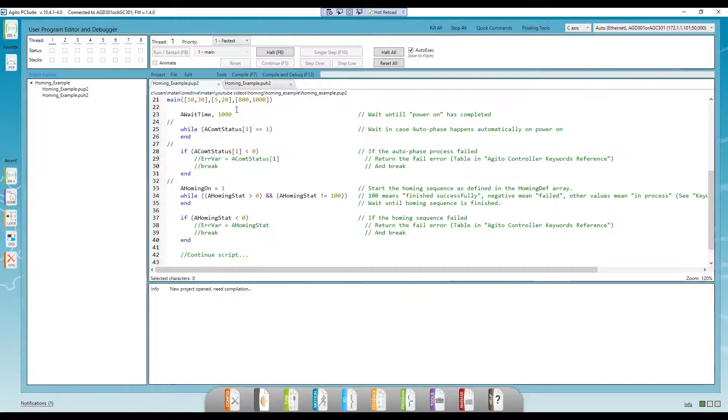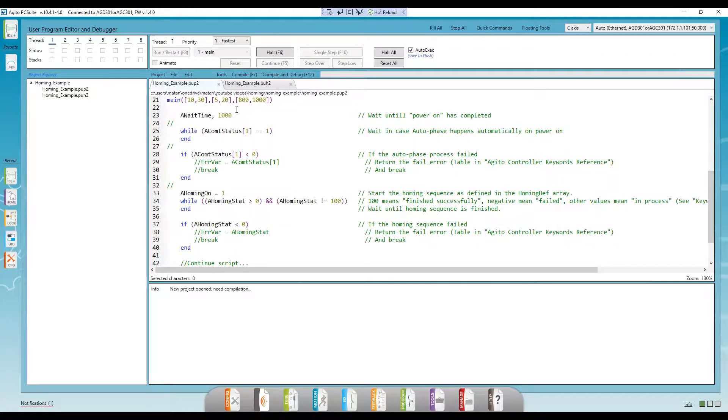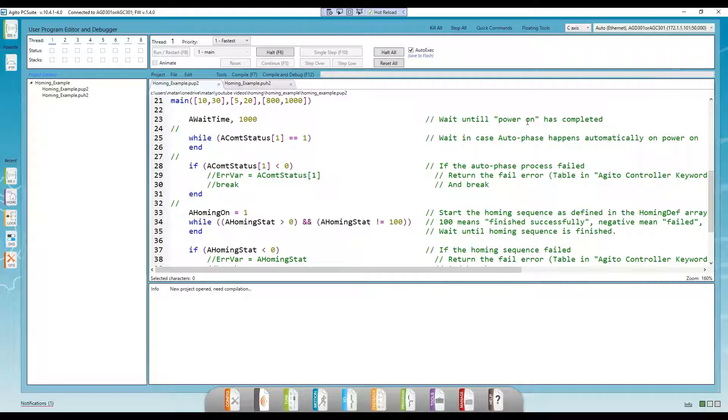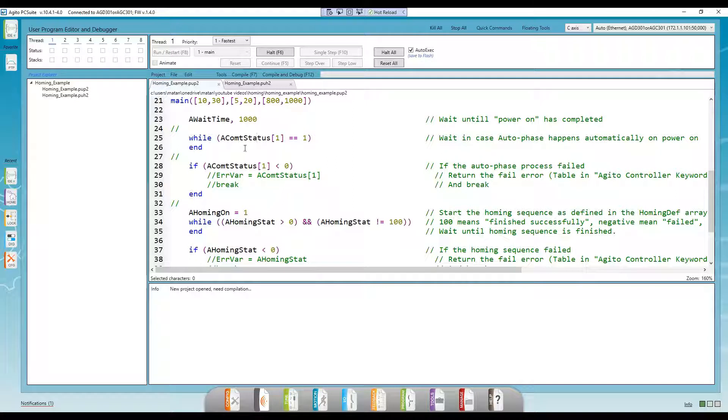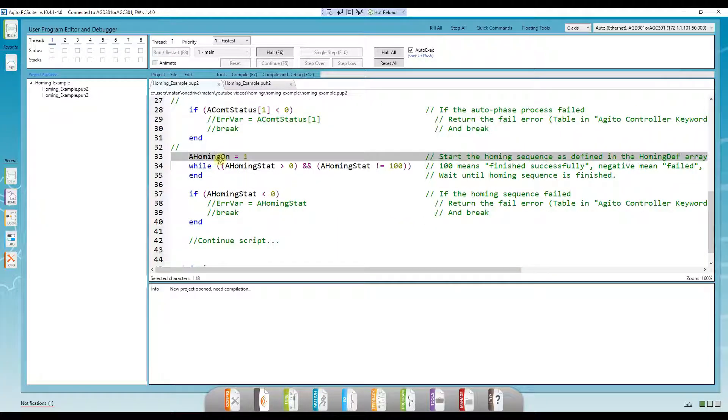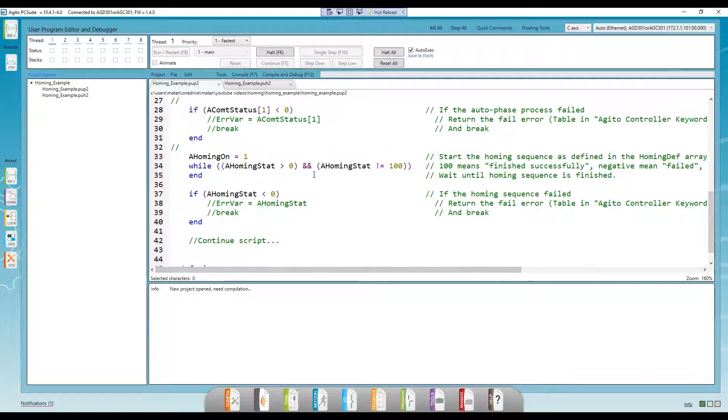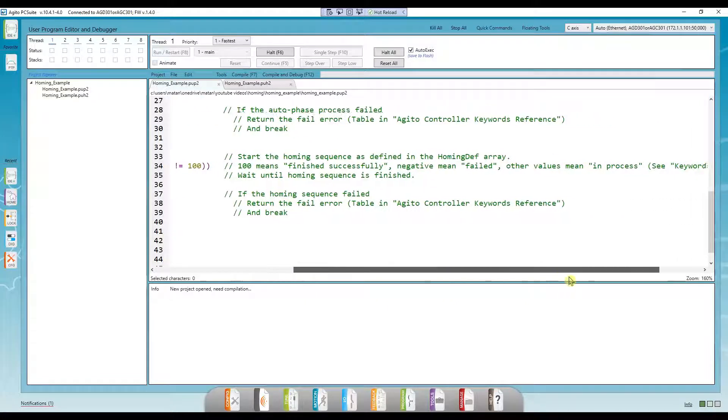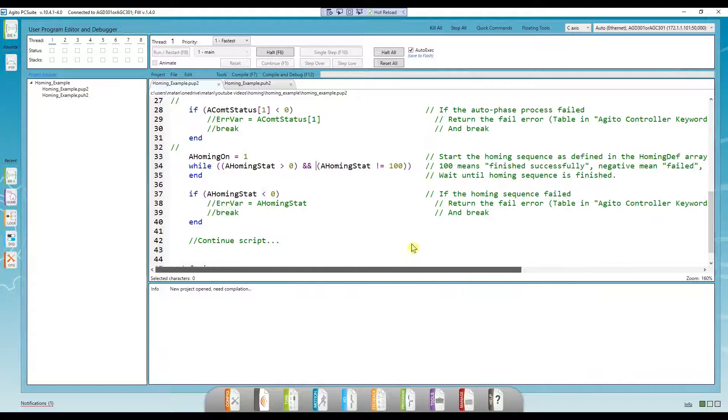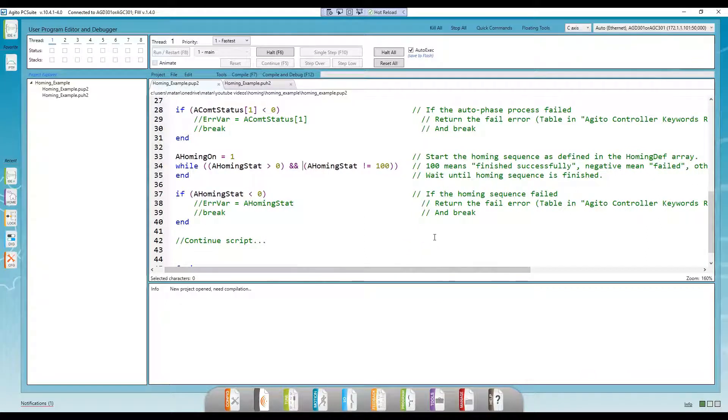Okay, one last thing I want to show you is running the homing sequence from our IDE plus while checking the homing status to know when we can continue with the rest of the code. We'll start by waiting for the powerup sequence to finish. Next, we'll wait for the autophase process to finish. Then we'll run the homing sequence as defined in the homing def array. And finally, we'll check the homing status keyword to find out when the homing sequence has finished. We can also put this piece of code in a function like we did before and execute it at the beginning of the main task.